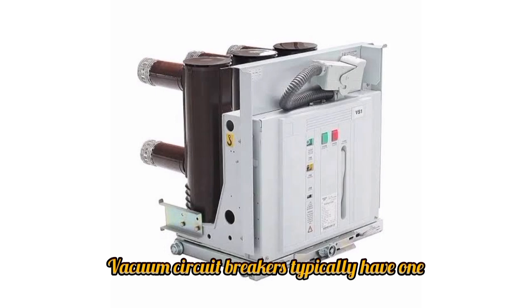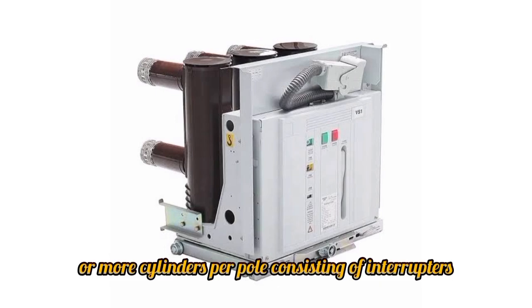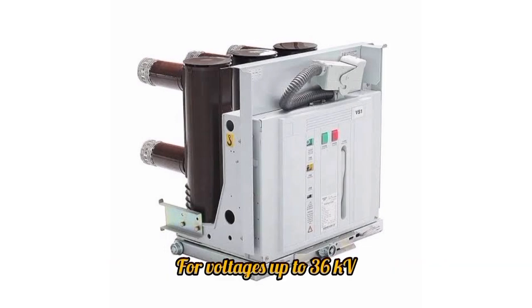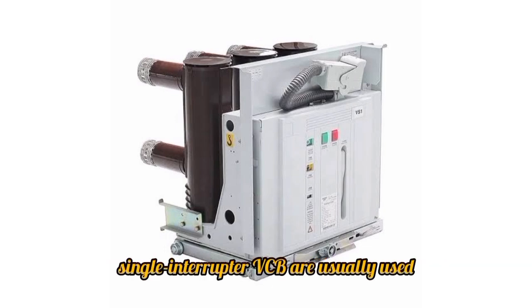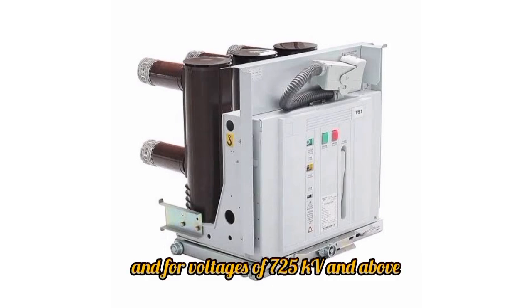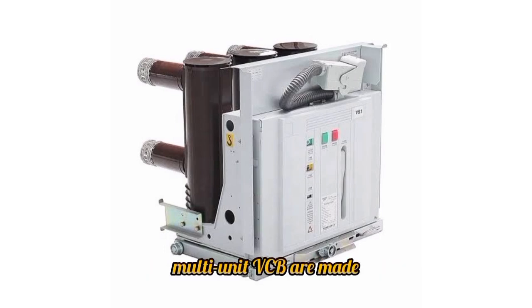Vacuum circuit breakers typically have one or more cylinders per pole consisting of interrupters. For voltages up to 36 kV, single interrupter VCBs are usually used, and for voltages of 72.5 kV and above, multi-unit VCBs are made.